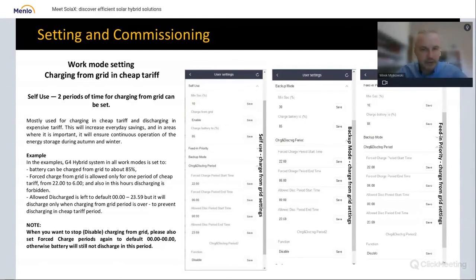As I said before, forced charge period times are just pointing exactly for the inverter in which hours it can start taking energy from the grid and load that energy into the batteries. You can also set it to what percent of capacity to charge the battery - if you set 85, it will charge to around 85 and then stop. But if at the set hour the battery is already at 85, it won't charge because it's already done. So it's not that it will charge anyway no matter the battery state of charge - if the battery is already charged, it won't use that time.